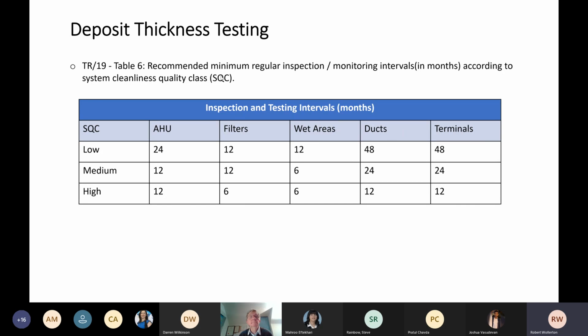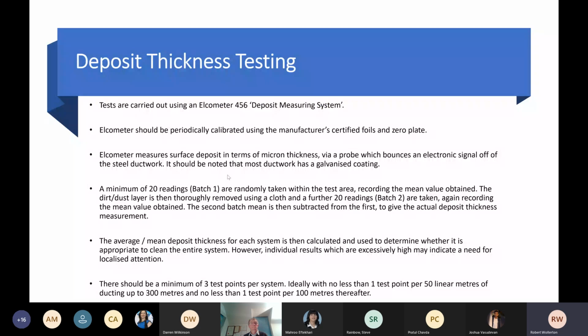Then we come on to dust deposit thickness tests and regular inspection monitoring intervals in months. This defines when the guidance in TR19, in terms of the classification, recommends you should be inspecting various elements of your ventilation system. This high, medium, low classification was fantastic for the industry and gave people some excellent guidance. So the dust deposit thickness test, what is that? The instrument was designed to measure the thickness of paint on cars. We go in and carry out the methodology detailed here, and we do 3 test points per system, which gives you an average reading for that particular supply or extract system.